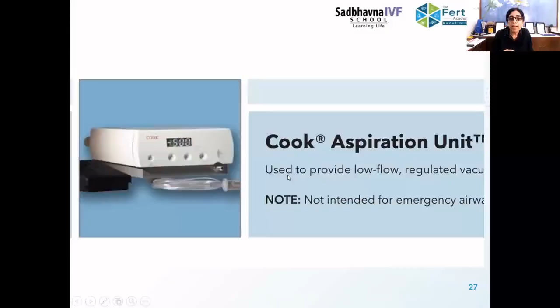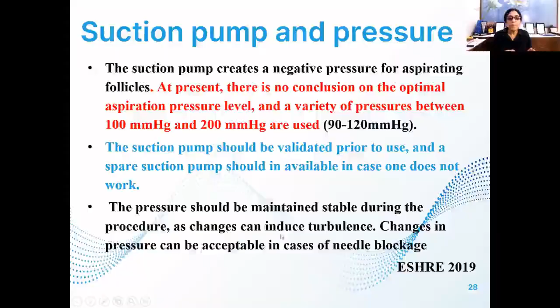The suction pump creates a negative pressure for aspirating follicles. At present, there is no conclusion on the optimal aspiration level, and a variety of pressures between 100 and 200 are used. The suction pump should be validated prior to use, and a spare suction pump should be available in case one does not work. Now, what do we mean by validating a suction pump? We can validate the thermometers, the pressures, the CO2 levels, but how do we validate the suction pump? We'll be talking about that in another 2 or 3 slides. The pressure should be maintained stable during the procedure, as changes can induce turbulence. Changes in pressure can be acceptable in cases of needle block.